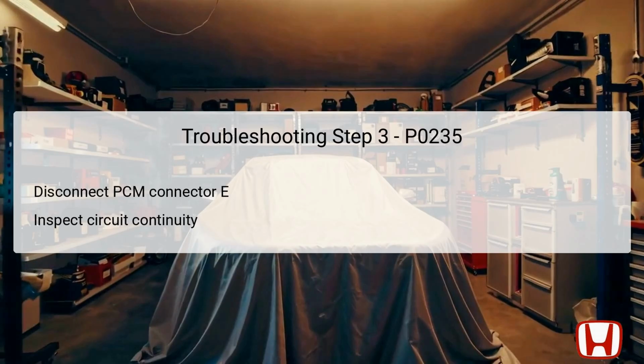After disconnection, the goal is to perform a continuity check on the VCC2 circuit. You want to ensure there is less than 1 ohm of resistance, which indicates the circuit is intact and functioning correctly. If the resistance is higher, it suggests an open circuit, requiring further diagnostics to identify the problem.